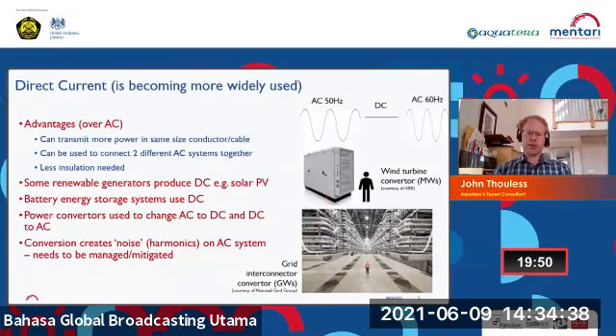This conversion process, which we've had to manage more over the years as we've introduced more converters onto the system, does create what we call noise or harmonics. The power electronics we use today are a lot more sophisticated than those used 30 years ago, and the level of harmonic content from them is a lot less. But that needs to be designed in and filtered out in systems, otherwise it can become a nuisance, both for the system itself in terms of creating heating problems, and also for users through things like voltage flicker on their supplies.